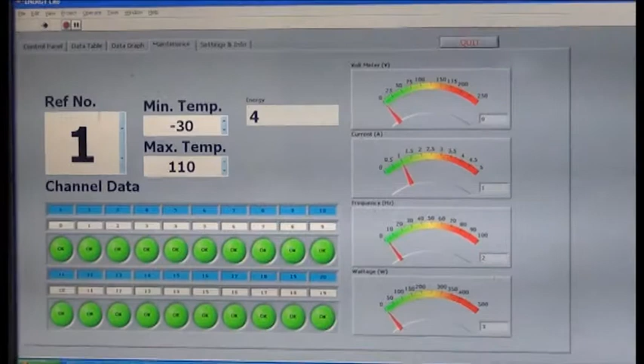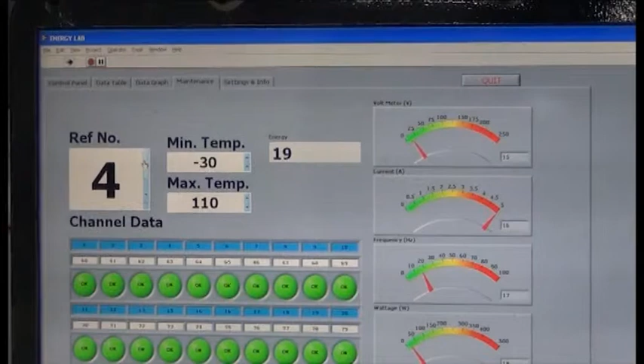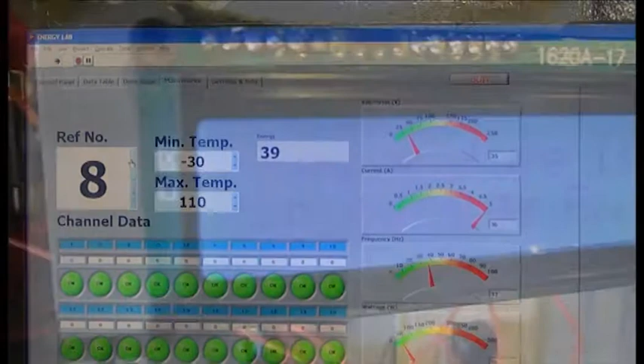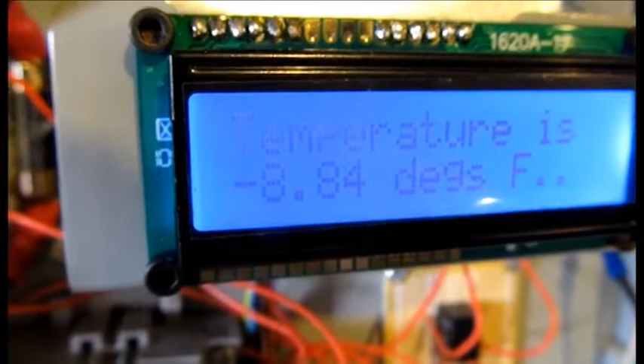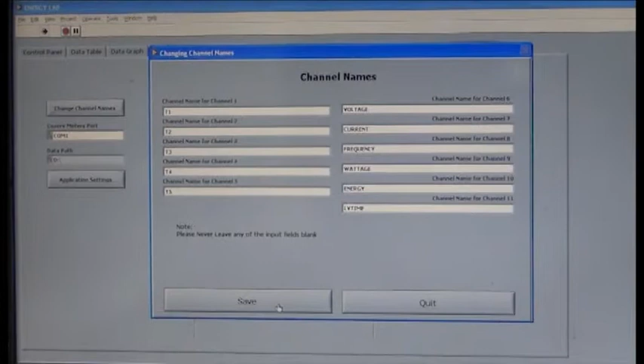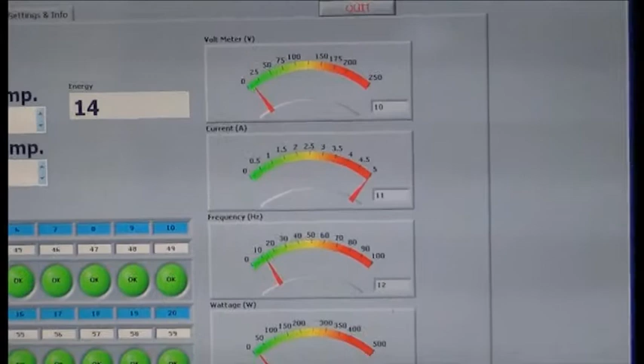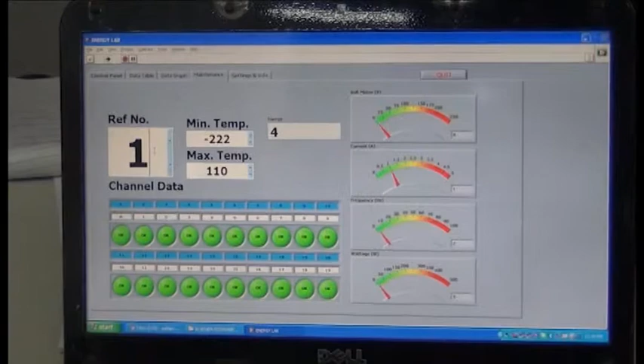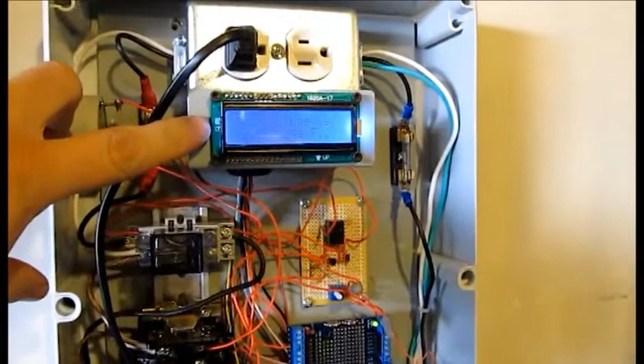The earlier systems were not capable of carrying out online calculations, like standard deviation, uncertainty in measurement, etc. The accuracy of measurement was limited to very coarse values and generally unacceptable as per NABL guidelines. They used different software and hardware to monitor energy and temperature separately using different standards and protocols, having no facility of expansion or modification. The earlier systems were hardware dependent, so the cost of investment had limited life. The software made in most of the laboratories was in closed architecture, hence not offering flexibility in changing test requirements. The system designed by our team is capable of using any standard hardware to suit any budget. We have installed our systems at various industrial locations all over India.